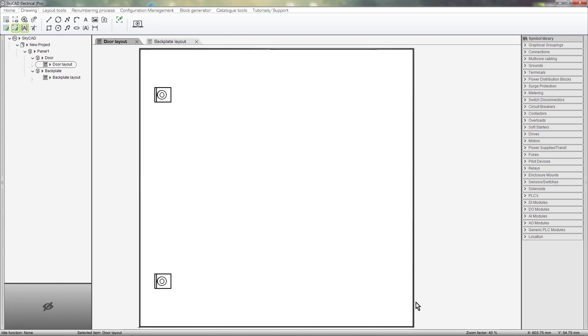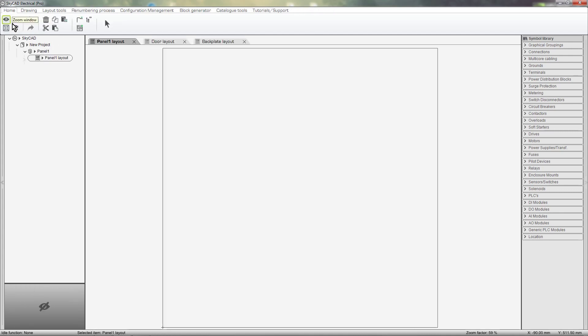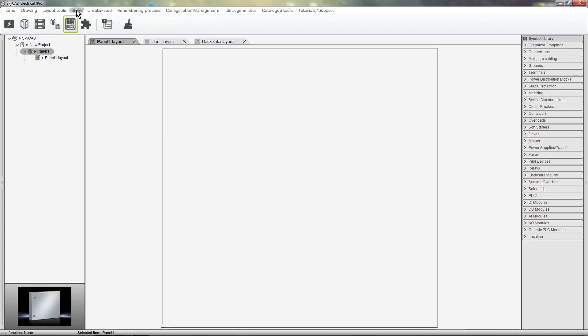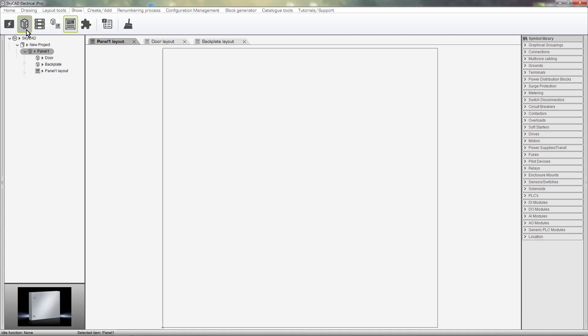At this point we could consider our enclosure complete and save it to our catalogue. But if you want to be more specific, you could go a step further and create a layout for the enclosure itself and show the Backplate Layout inside the Panel Layout. This can be handy if your backplate is smaller than your enclosure or if you have multiple backplates in your enclosure. Let's create a layout for this enclosure. You may have noticed the Door and Backplate disappear from the Tree View — this is to highlight the layout that we just created. If you want to view the Door and Backplate in the Tree View again, select the enclosure, click on the Show tab and select Sublocations. Hold the Control key to show the sublocations in addition to the Enclosure Layout.